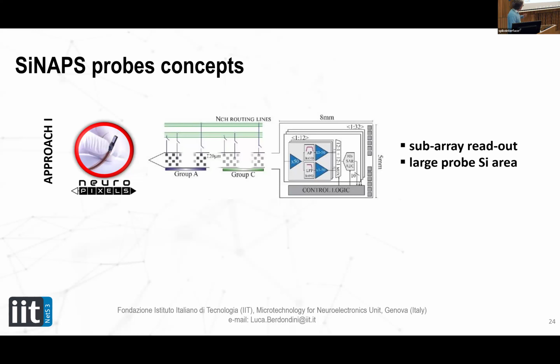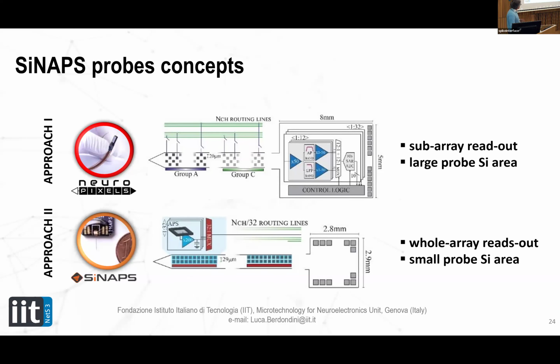What we have been developing is a concept where the front-end amplifier is integrated underneath each electrode, because our rationale was: if we place electrodes in the brain, we want to record from all of them, with full bandwidth from almost DC level up to 5K, just to give you numbers. This was a big challenge, and it allowed us to drop down the overall form factor of these devices and enable recording up to 1,024 channels, as we have right now.